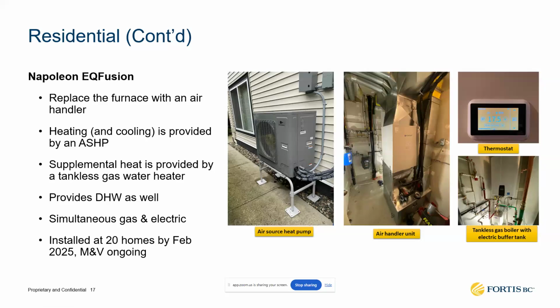And the additional heating will be provided by a tankless gas boiler. This tankless gas boiler serves a heating coil in the air handling unit and is controlled by a three-way valve. So your gas boiler will top up whatever heating the heat pump cannot provide. Again, this is a great help because we don't have to size our heat pump for the coldest day of the year. We typically size for cooling, and then we get whatever heat we can from the heat pump. But so far, it has been adequate for the heating needs of our customers.